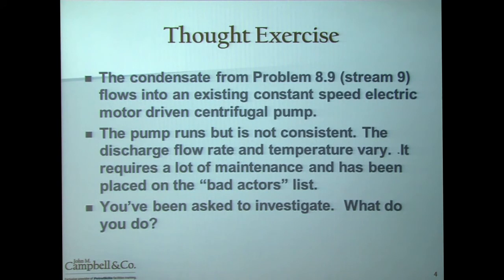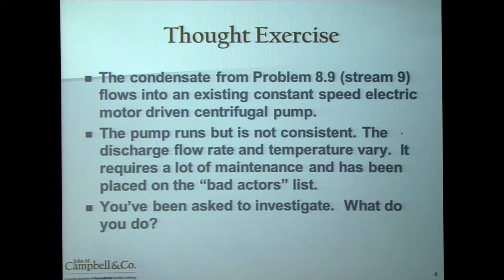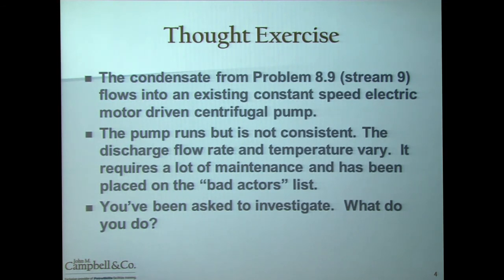Remember problem 8.9? That was the hydrocarbon dew point control unit that you evaluated in section 8, which was the energy changes. If you take the condensate from that hydrocarbon dew point control unit and assume that it flows into an existing constant speed electric motor driven pump, that particular pump runs but it's not consistent. The discharge flow rate and temperature varies quite a bit, it requires a lot of maintenance, and it's been placed on the plant's bad actors list. You've been asked to investigate. What do you do?